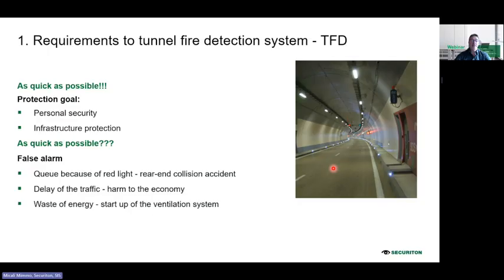Therefore, it's not good to have false alarms, and there is also waste of energy, of course. Because imagine, every time you have a false alarm, normally the ventilation starts to de-smoke the tunnel. That means everything is automated. So if there is a false alarm, you have to start the jet fans, and these consume a lot of energy to bring them to maximum power and velocity. Therefore it's also a waste of energy, and this we have to avoid too. And finally, every time you have an alarm, you automatically activate the fire brigades and the rescue team, because you never know if it is really an alarm or not.